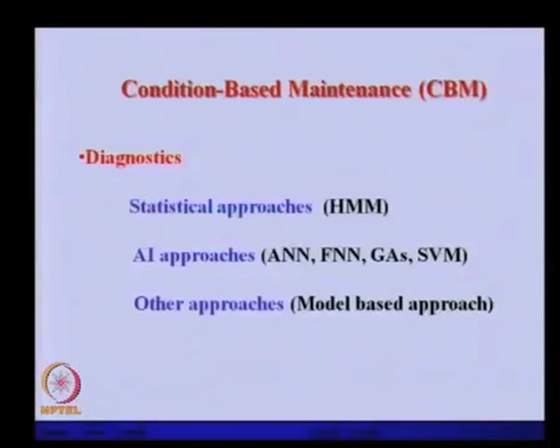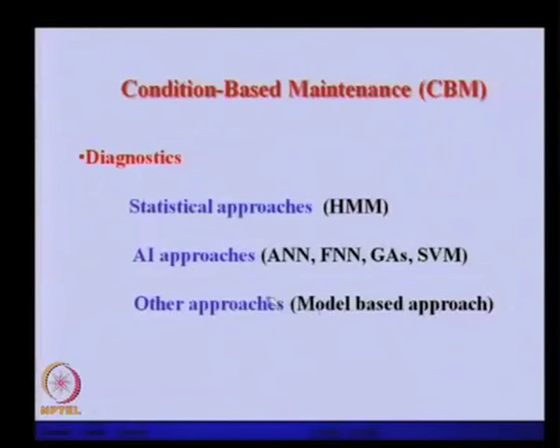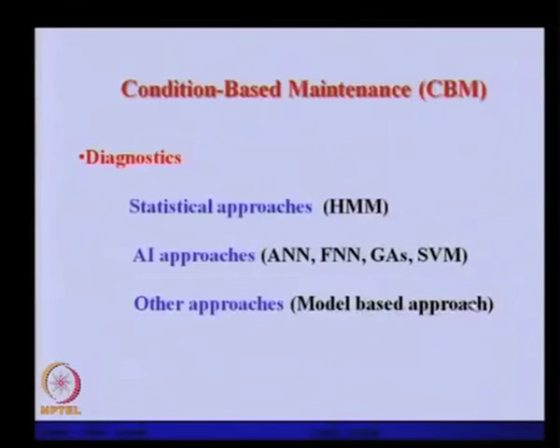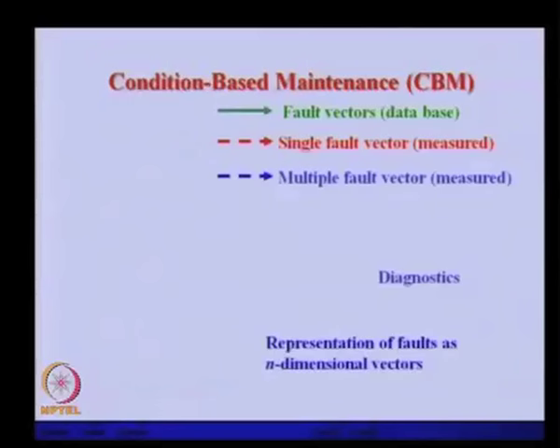For diagnostics, various approaches are used: statistical approaches like hidden Markov processes; artificial intelligence approaches such as artificial neural networks, genetic algorithms, and support vector machines; and model-based approaches. For faults like unbalance and misalignment, mathematical models can be built, and the vibration from the actual system can be curve-fitted to the model to determine whether the fault is present, its severity, and its quantification. This model-based approach is an active area of research in the rotor dynamics field.